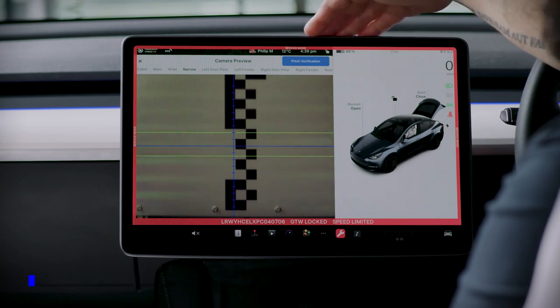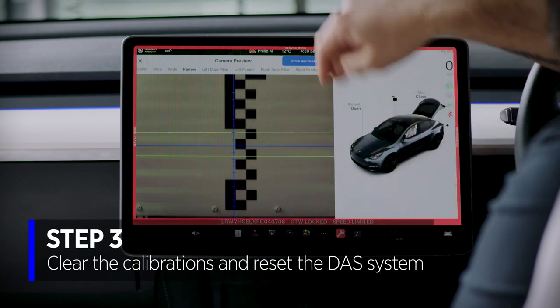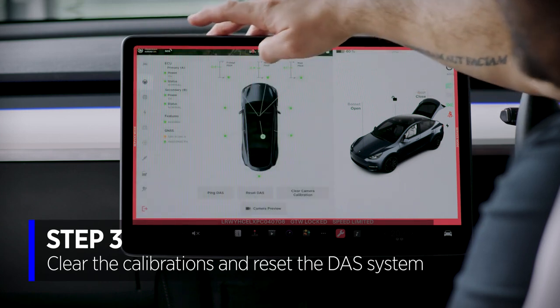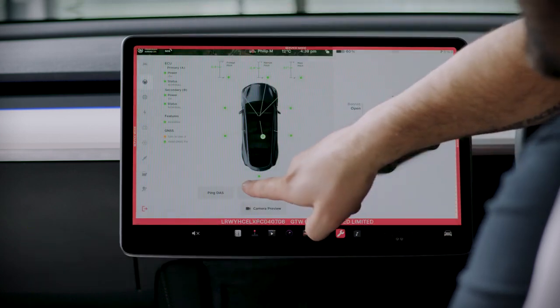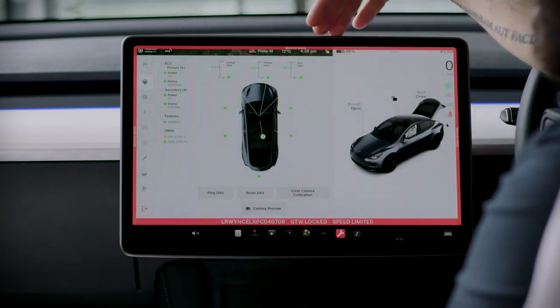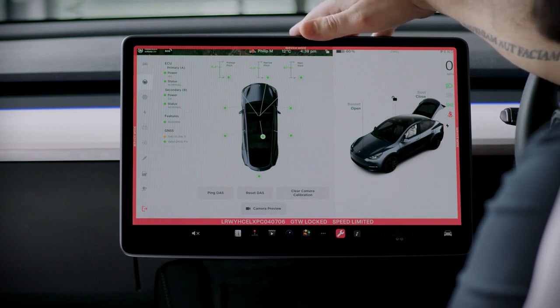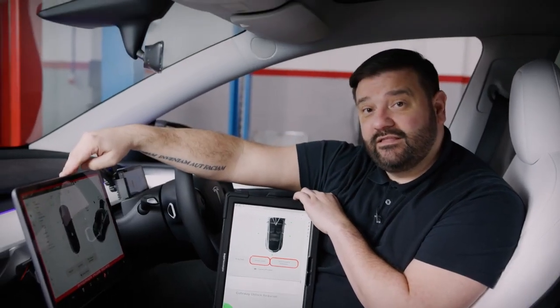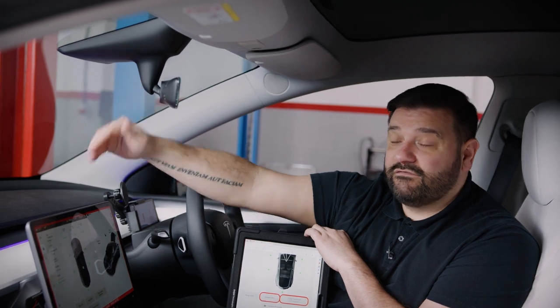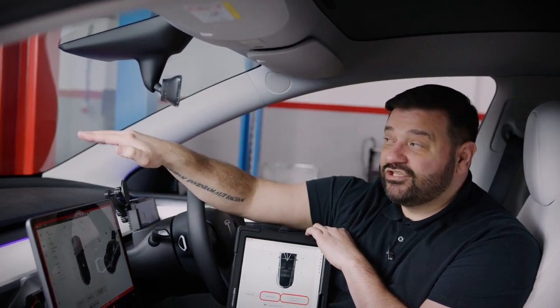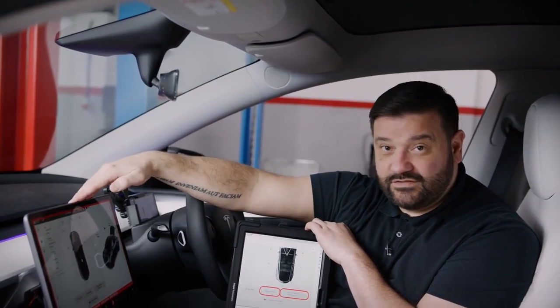Now to make the adjustment, it's quite simple. We clear the calibrations first. So if we go back off here, we reset the DAS system, we clear the camera calibration, and then make the adjustment. There is a small adjustment screw behind the mirror. Drop the mirror off, grab the adjustment screw, and adjust it until it comes within tolerance.